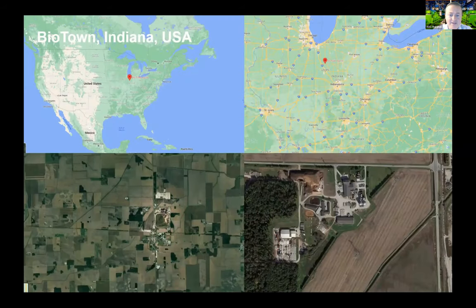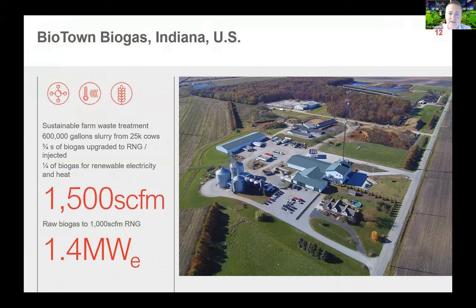The second case study is in Indiana, USA, close to the previous speaker's location. This is BioTown — a brand new hybrid project using CHP and biogas upgrading facilities. A large series of cattle farms in the local area provide slurry from 25,000 cows — 600,000 gallons of slurry. Three-quarters of that is upgraded to RNG for export and one quarter is used for self-consumption, combining 1,500 standard cubic feet per minute of raw biogas into 1,000 standard cubic feet per minute of RNG, plus 1.4 megawatts of electrical output and a similar amount of thermal.